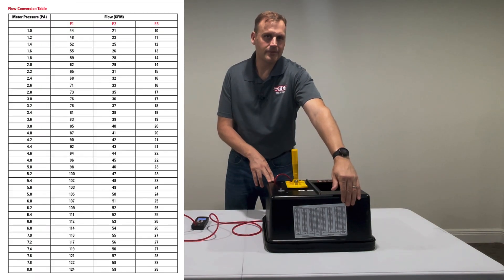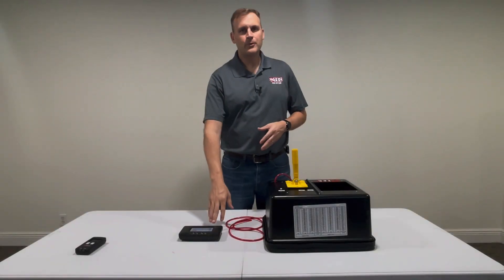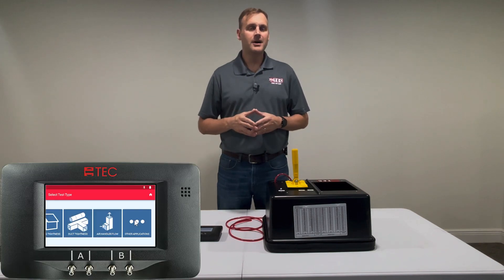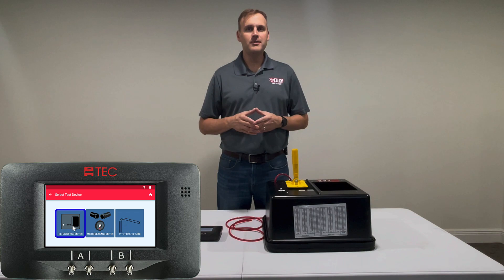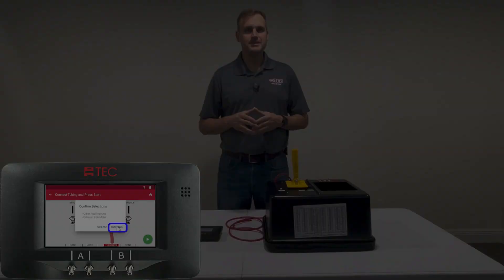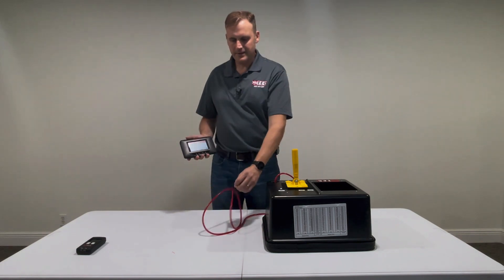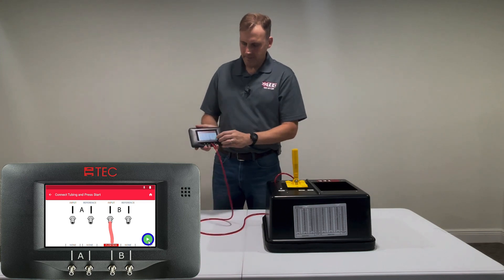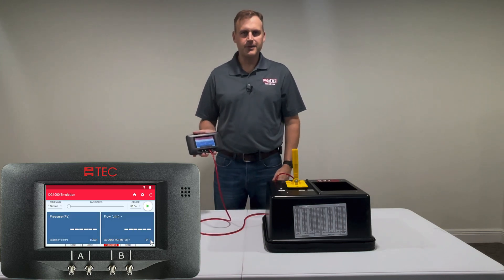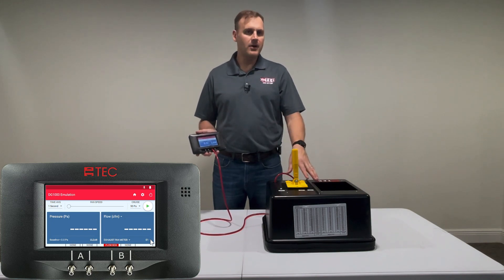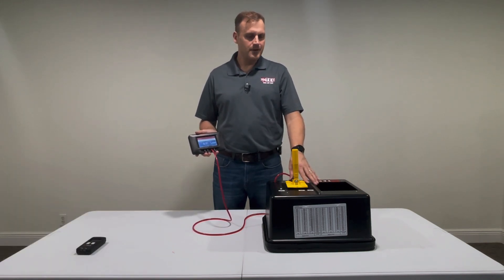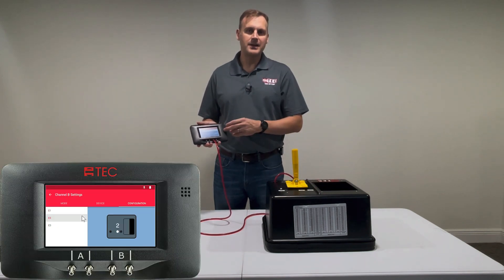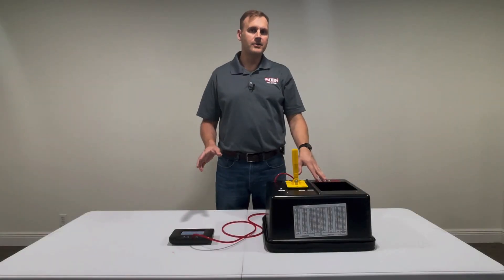If you'd like to use the DG1000 gauge, power it up, then select Tubing Assistant, Other Applications, Exhaust Fan Flow Meter, and confirm your selections. Connect the other end of the tubing as shown on screen, hit the play button, and advance to the screen that will show your flow measurement. It's important to note that if you change the position of the access door, you will also need to make that setting change in the gauge.